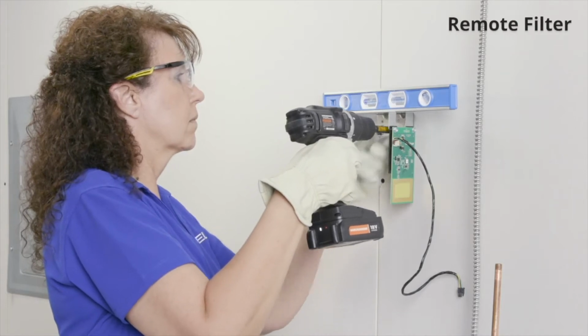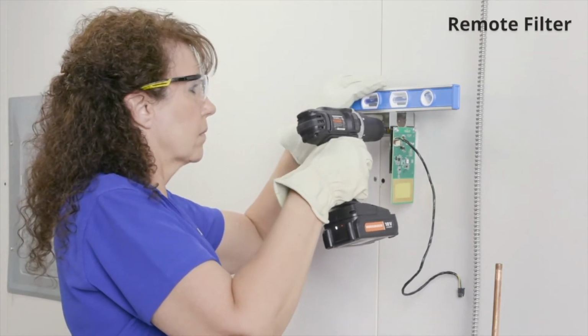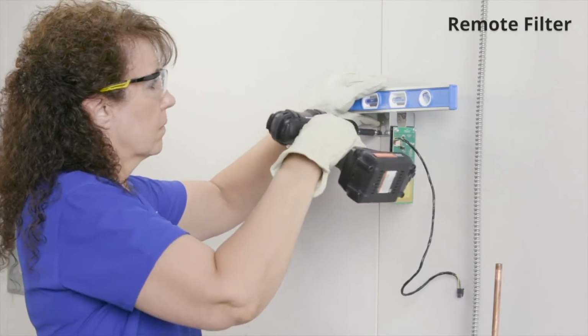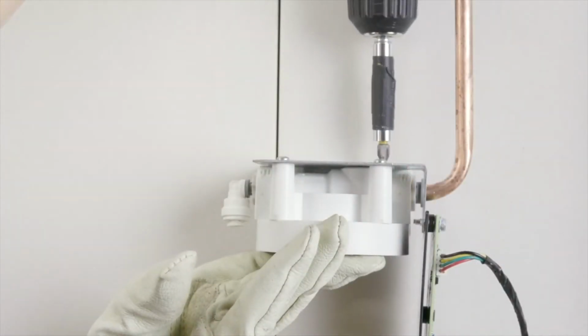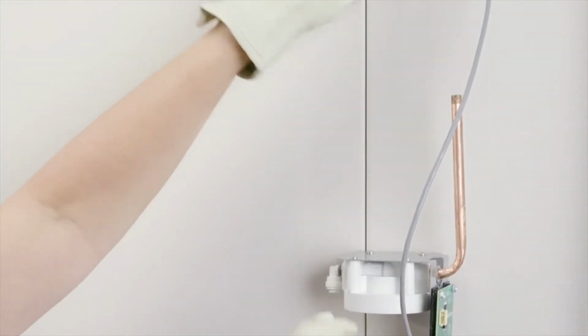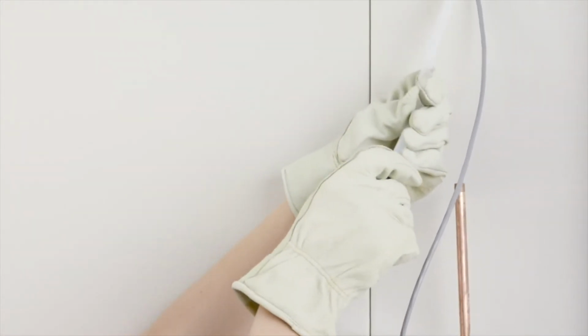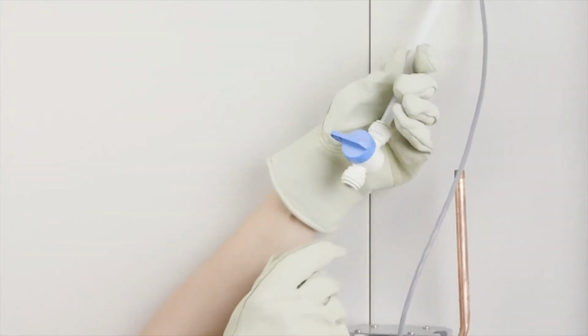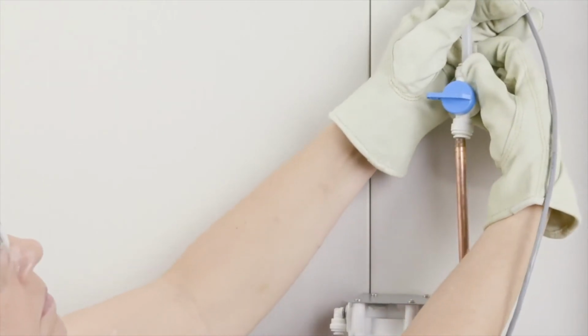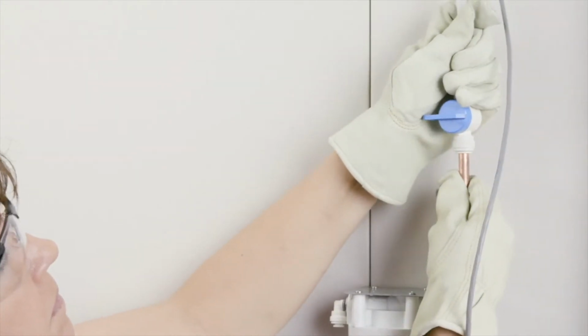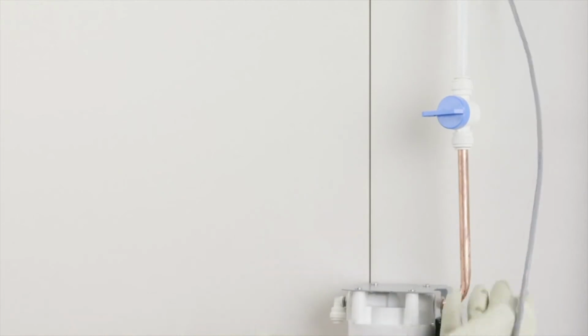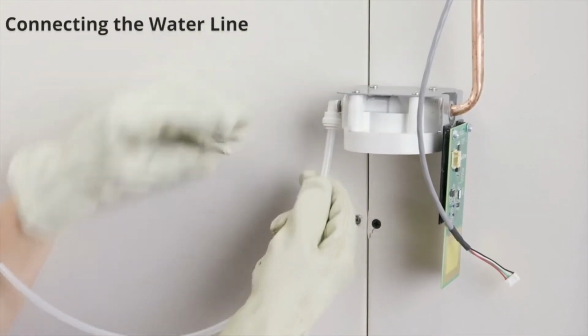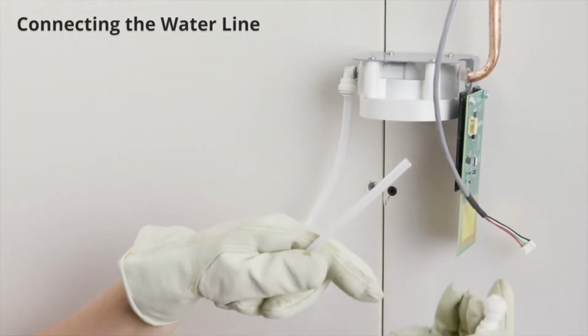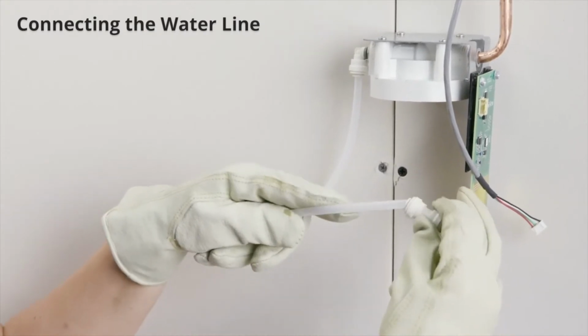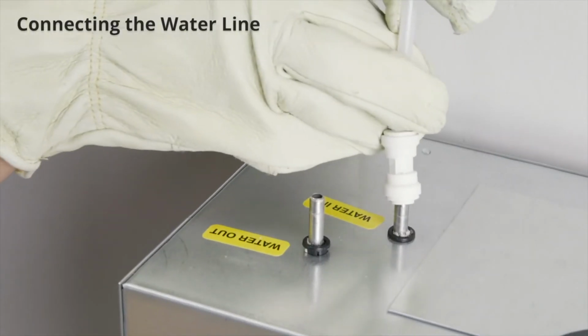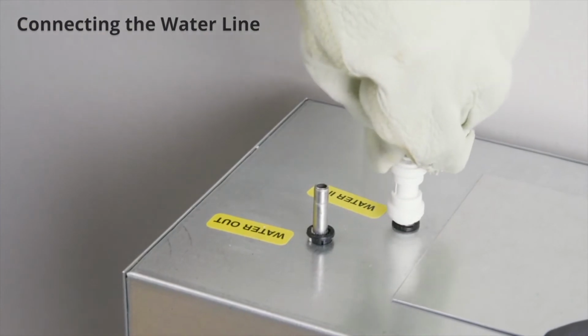Next, securely mount the filter head vertically on a wall or other supporting structure near the chiller. Connect a 3/8-inch water supply line, copper or plastic, to the quarter-turn shutoff valve. Then connect the water shutoff valve to the water inlet to the remote filter. Connect a 1/4-inch water line, copper or plastic, to the outlet connector of the filter. Then connect the remaining end to the remote chiller water inlet.